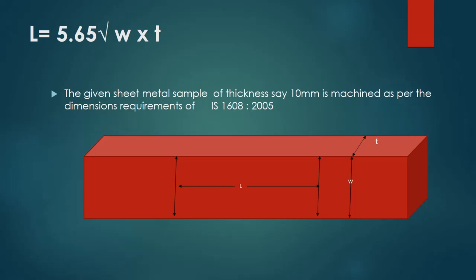The gauge length is given by the formula 5.65 multiplied by the square root of the original cross-sectional area. Here the cross-sectional area is the multiplication of W and T, that is the width and thickness of the rectangular specimen. Once the gauge length is measured, it is marked on the center of the specimen and it is gripped at the two ends and pulled apart in a machine by the application of a load.